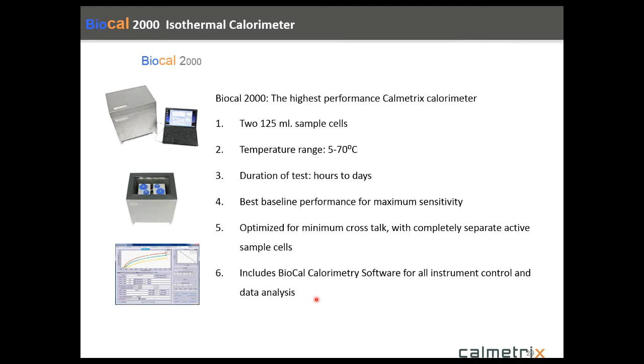The 2000 is our highest performance instrument. It has the best baseline performance, so it has the maximum sensitivity to picking up the smallest amount of change in the baseline, basically. It's optimized for minimum crosstalk because it uses 2 individual calorimeters with completely separate cells, so that's why this is the highest performance instrument. The instrument comes with the software. It comes with actually a computer. It's a turnkey system. You can get this system, get it out of the box, get it up on the bench, and within a half an hour you're ready to go, or you're at least got the instrument equilibrating. Very easy to install and use the instrument.